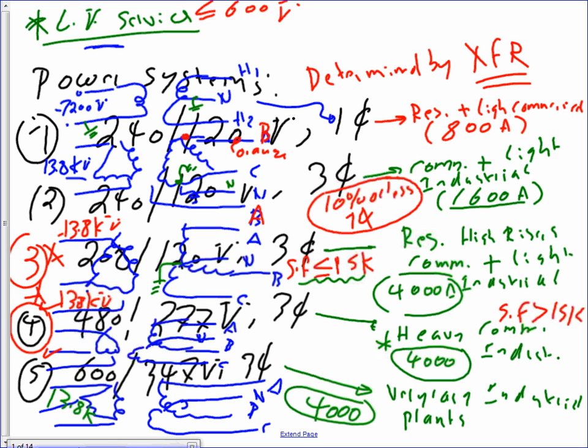The reason why I'm telling you this, guys, you're designers, not just drafters, so you're going to be in a meeting one day when you become a project manager, and they will be asking you to decide what type of voltage system we need for this building. So these will give you a rough idea of the types of systems that we use. Square footage of 15,000 or less, residential, high-rises, downtown Minneapolis, all these risers that you do, commercial plus light industrial up to 4,000 amp.